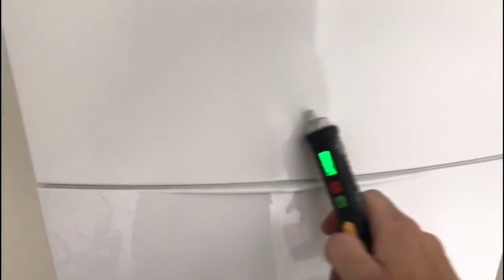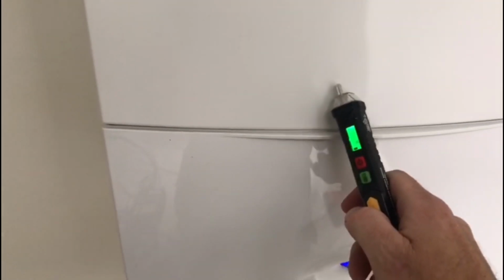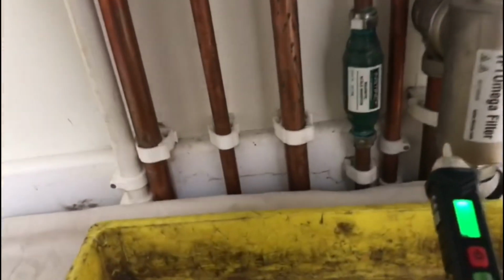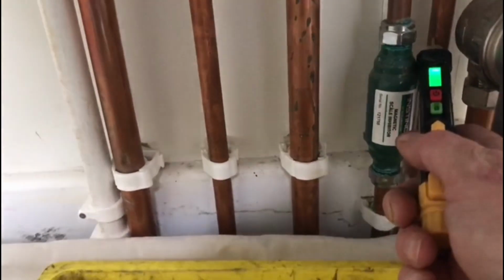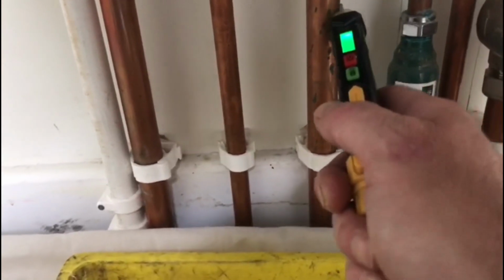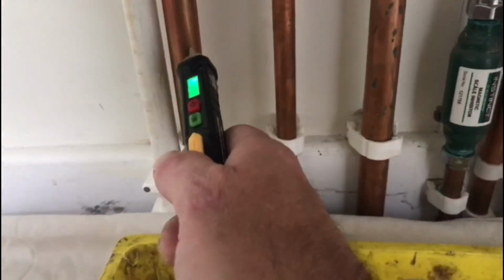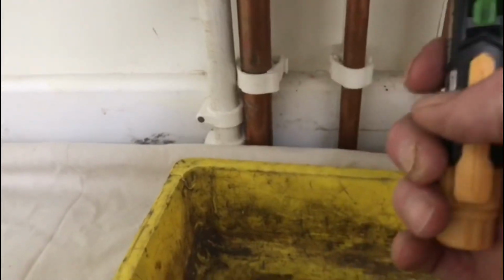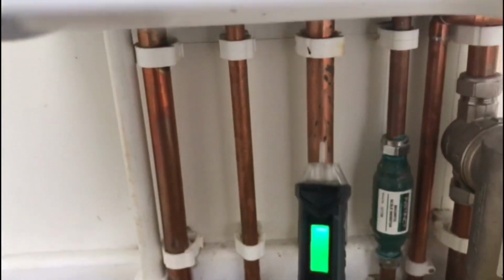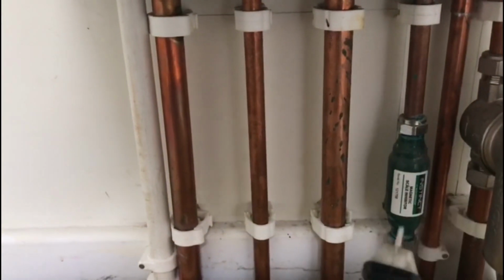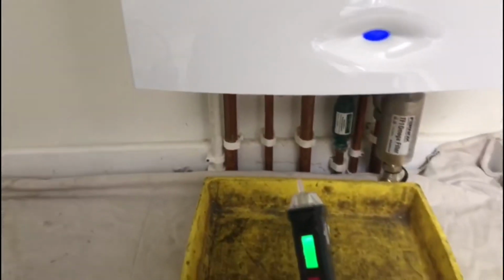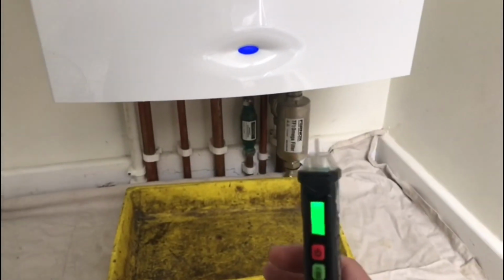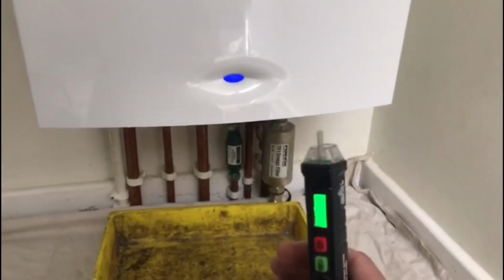It's painted, so it's insulated really. This bit's plastic, so not much point testing that. But test around the case. But also, very important, test the metal components going into your boiler, and test the chassis underneath your boiler. If you don't test these parts, they may be live and you may come into contact with them and touch them. You've got to make sure that there's no way you can get a shock from it.